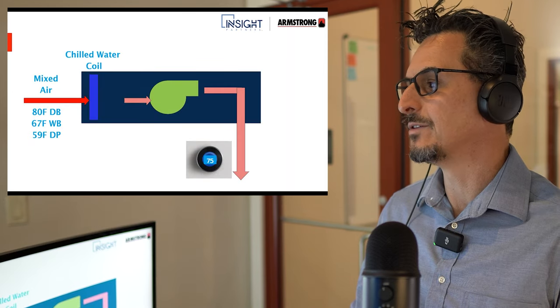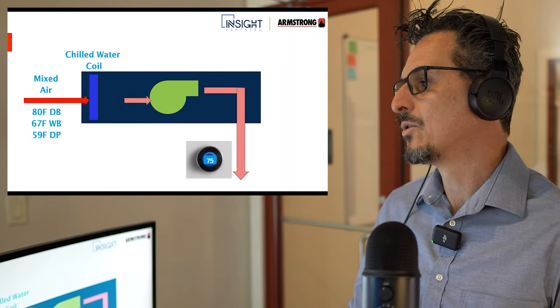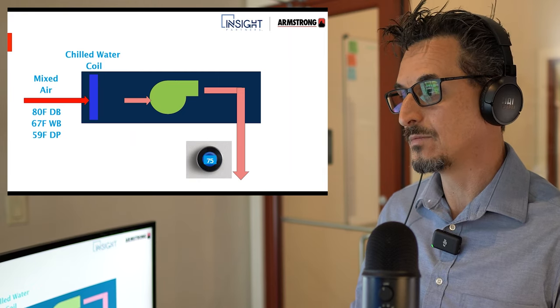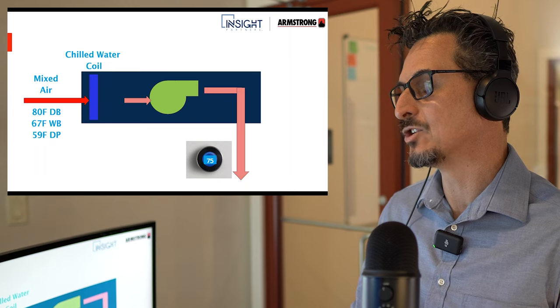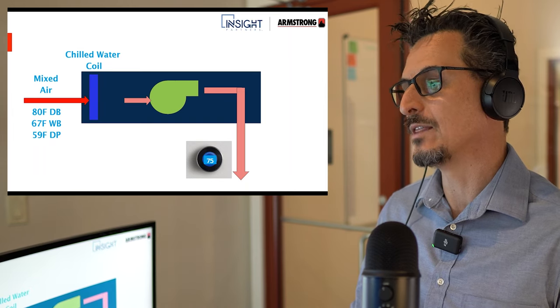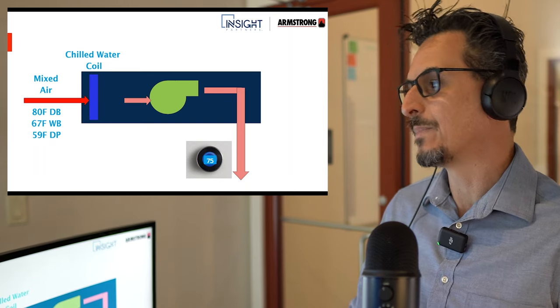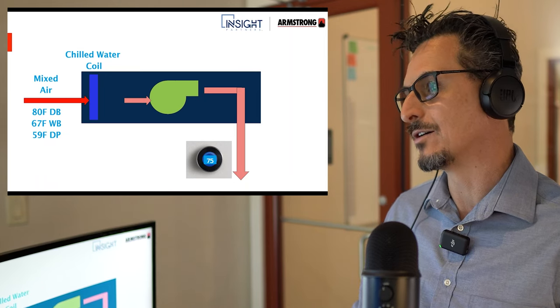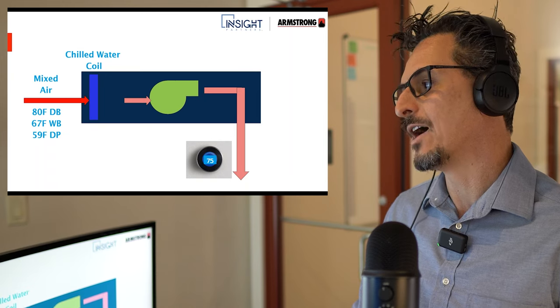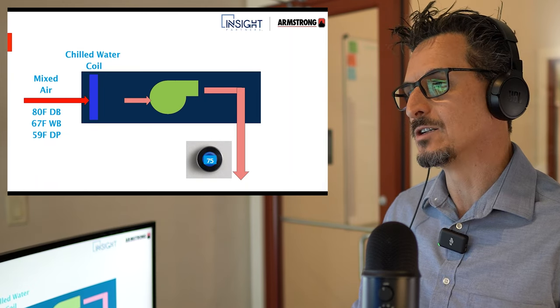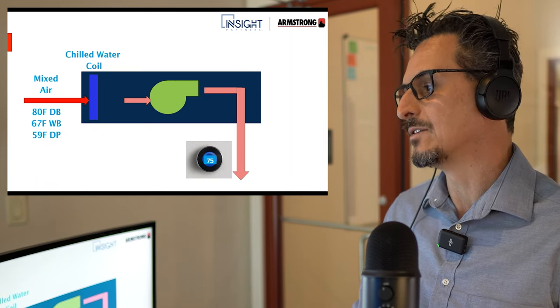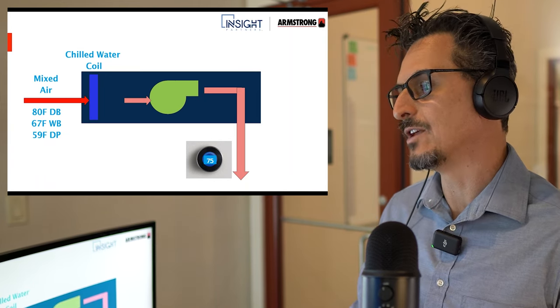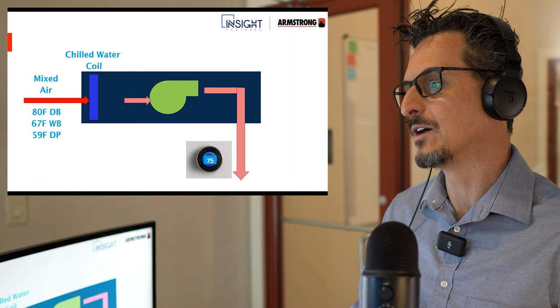Throughout most of this presentation, we're going to focus on a constant volume chilled water air handling unit — your typical modular climate changer type product or a larger blower coil, maybe a very large fan coil. It has a chilled water valve that is modulating or on/off, and a constant volume supply fan. The next psychrometrics presentation will concentrate on VAV, but for now we'll stick with a constant volume unit.